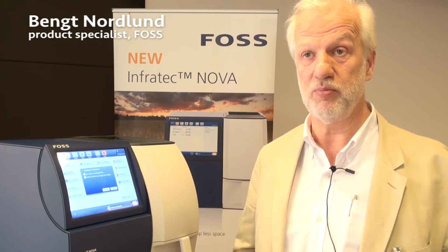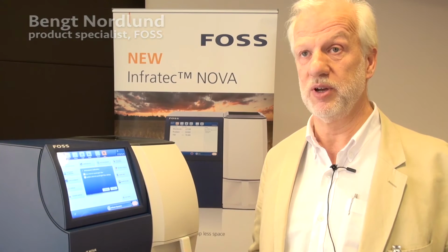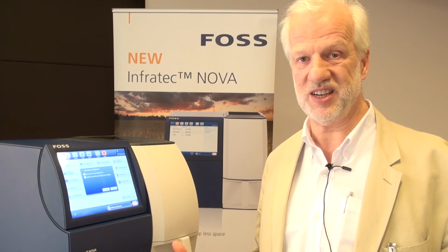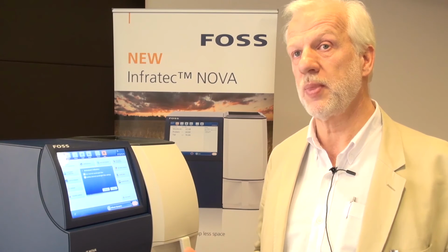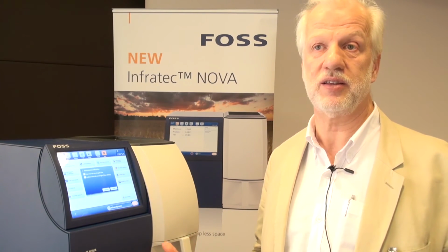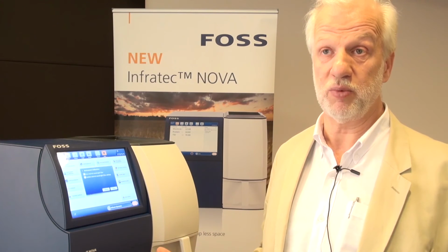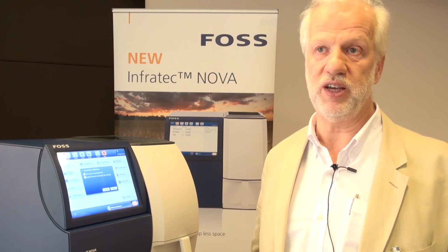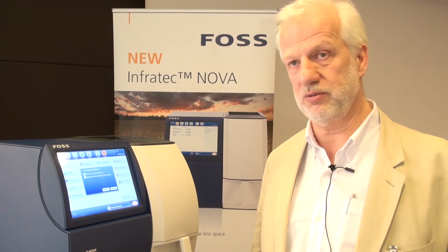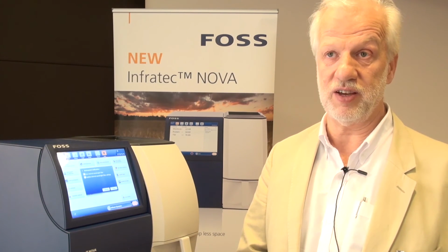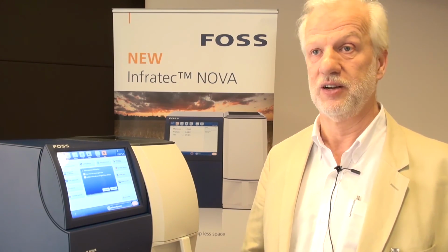We now have an instrument calibration which means we have a built-in wavelength calibration filter, making the instrument stable over a long time. The wavelength is checked during the self-test diagnostic, and if it's out of limits, it will tell you that you need to do a new wavelength calibration, so you can do that. This means that even if you have the instrument for several years, it will not drift. So it takes away both the need for yearly standardization, and also the need for standardization between instruments, because all instruments are identical.